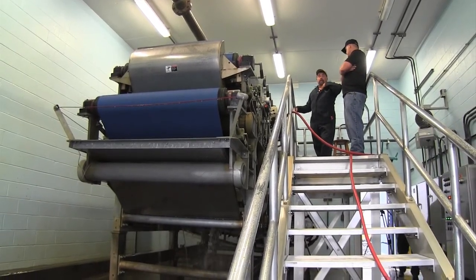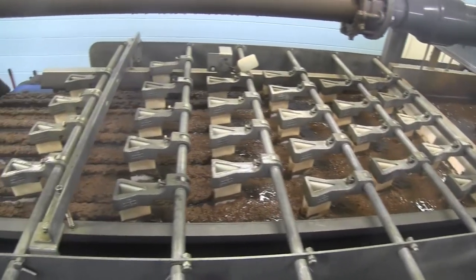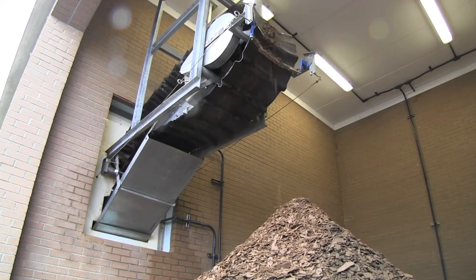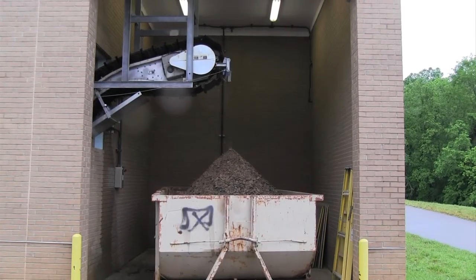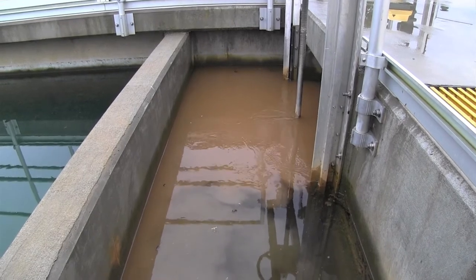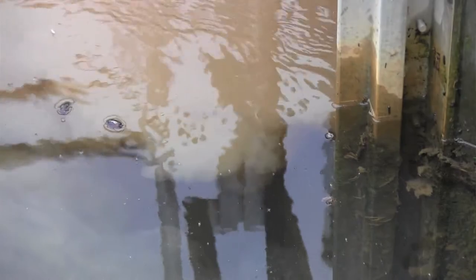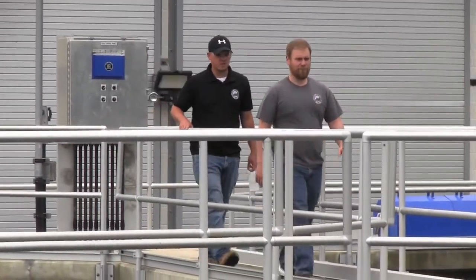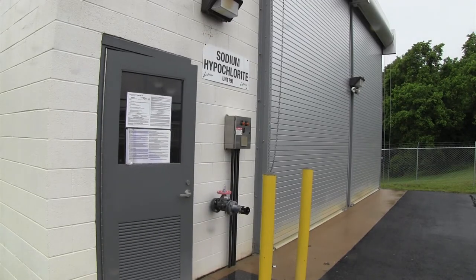Because we're removing so many more particles and organics, we have increased our sludge load. We've been able to get better dewatering, and we're using a lot less polymer to separate the water and sludge, just because of optimizing dosages. When I first came here, we weren't getting the removal of organics out of the system. Now, with this pack and being able to optimize our dosage, we test on our raw side and we'll have two to three milligrams per liter of TOCs, and we'll have non-detect at the end of the SED basins. With our disinfection byproducts, we were getting high TTHMs and HAA-5s. Now that we've dropped our chlorine on our SED basins, removing 99% of organics, there's nothing for those TTHMs and HAAs to form to, so they have dropped very significantly.